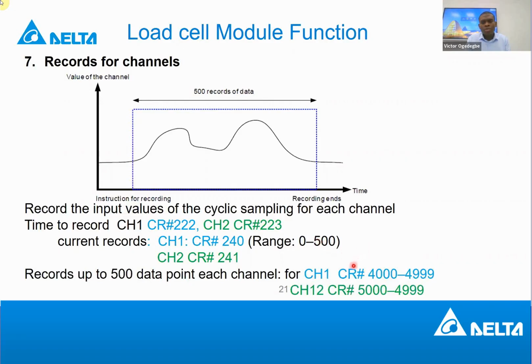And then there's the address where you can see those 500. For channel 1, you have recorded 500 different weights that you measured. So where can you find them? From 4,000 to 4,999. That's for channel 1. If you read this register range into your PLC, 500 registers, you can get which one. The record is stamping each register, based on the time you specified. If you specify 1 second, it will take longer. It will stamp, stamp, stamp, and then you can get them from here. And once you've got them from here, you can do what you want with them.